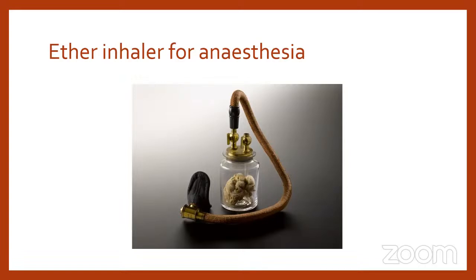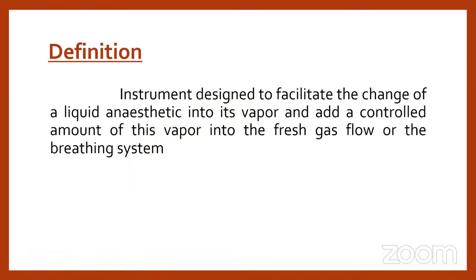So this is the ether inhaler used back in the day. Basically, it consists of a jar which contains cotton balls dipped in ether solution, and the fumes will be coming out of this ether, and the patient will be made to inhale those fumes through the mask which is provided in the basic vaporizer which was used in 1846. So what is a vaporizer? The definition is the instrument designed to facilitate the change of a liquid anesthetic into its vapor and add a controlled amount of this vapor into a fresh gas flow or the breathing system.